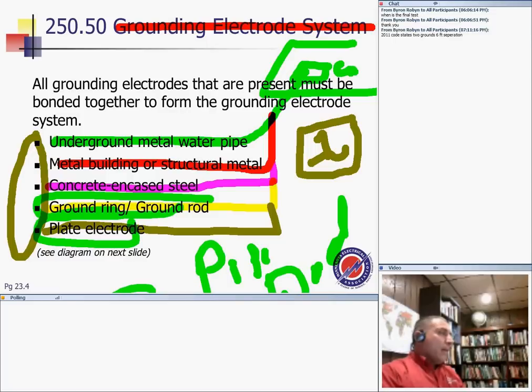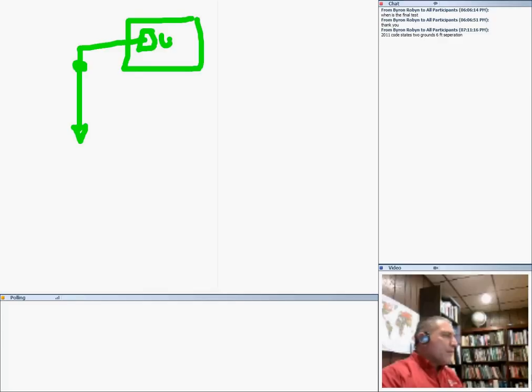2011, guys, they changed slightly the language. They said you need two, unless you can prove to the inspector that the impedance, the resistance to ground, is less than 25 ohms. But you have to have a machine. So if I want to go argue with the inspector, here's my pipe here, and I have my ground here, and I'm going to tie it only to right here. I need one. If I can prove that the resistance of this system is equal or less than 25 ohms, then I don't need another wire.